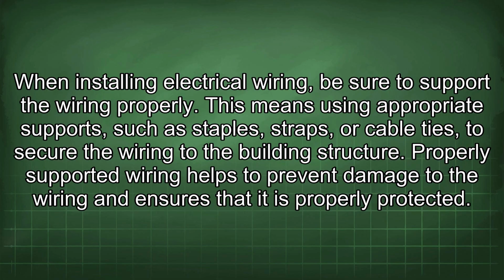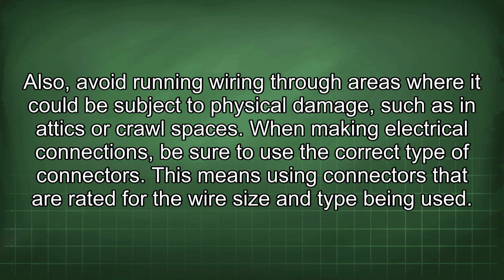When installing electrical wiring, be sure to support the wiring properly. This means using appropriate supports, such as staples, straps, or cable ties to secure the wiring to the building structure. Properly supported wiring helps to prevent damage to the wiring and ensures that it is properly protected. Also, avoid running wiring through areas where it could be subject to physical damage, such as in attics or crawl spaces.